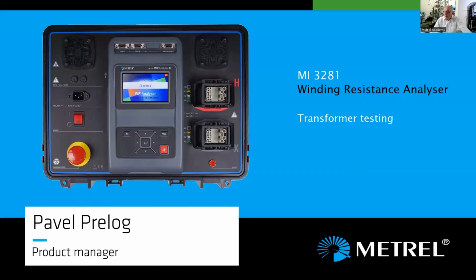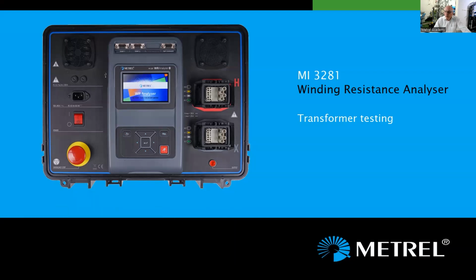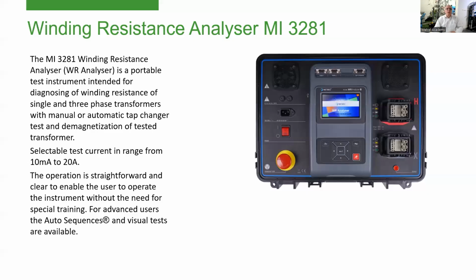Thank you, Tamara. As Tamara mentioned, today I will introduce you to a new product, the MI3281 Winding Resistance Analyzer. This is an instrument for which the name itself tells you that it is for measuring the winding resistance. This time without any limitations in the size or power of these transformers. We can test with scalable current from 10 milliamperes to 20 amps.